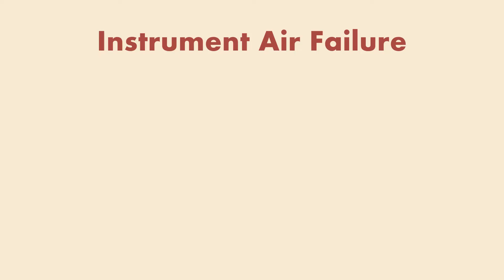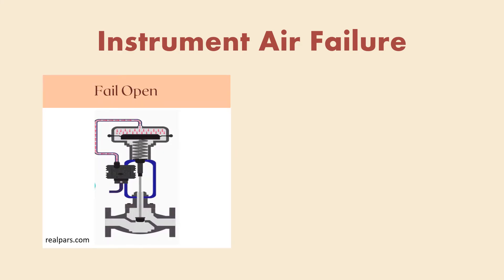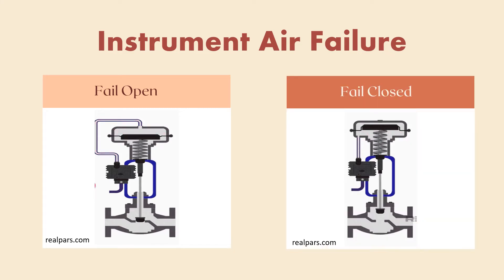So what if, for any reason, the instrument air system fails? This means that there shall be no air supply to the valve and the actuator won't work. The valve would be either totally open, totally closed, or it stays in its last position. This means that we should be ready for this scenario. When the instrument air supply is cut, would it be safe that the valve is fully open, or that it shall be fully closed, or that it stays at the last position?